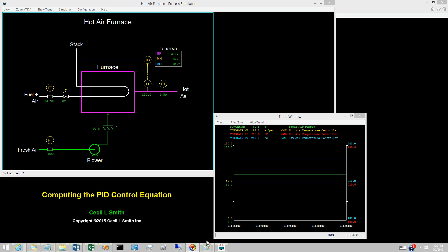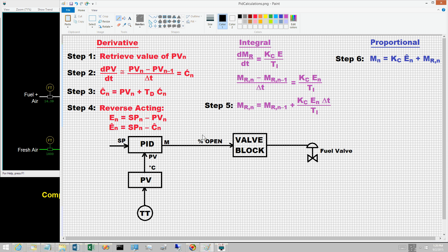The difference equations used in digital controls are approximations to the differential equations presented in previous videos. They are computed on a time interval known as the sampling time, delta t. An iteration is one execution of the difference equations. The values computed on an iteration are designated by a subscript: subscript n is the current iteration, subscript n-1 is the previous iteration, and subscript 0 is the first iteration following a switch to auto.